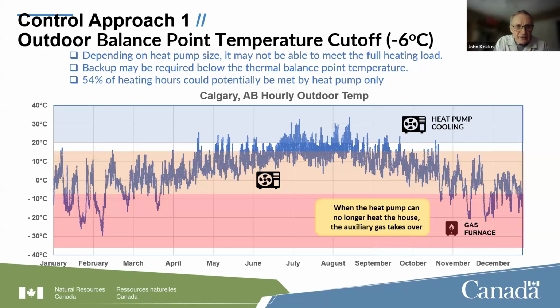The interesting thing here is if we ignore the summertime, when we're not going to turn heating on most of the time anyway, we do get over 50%, about 54%, of the hours covered by the heat pump we're using in this example. And only 46% or so comes from gas heating. The other nice side of heat pumps is that because they do reverse, we get heat pump cooling, so we can get air conditioning in the summertime with the same unit.